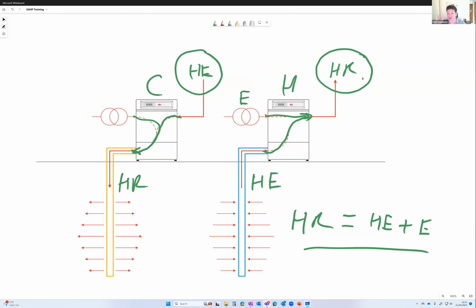So given that heat being extracted from the building or rejected into the building, how much pipe do I need to put in the ground to make sure this system is sustainable in the long term? We also have to add in the properties of the heat pump, because the ratio of electrical energy plus your heat of extraction, your heat of rejection, changes by different products. Different refrigerants, different heat exchanger architectures, different compressors have different properties.